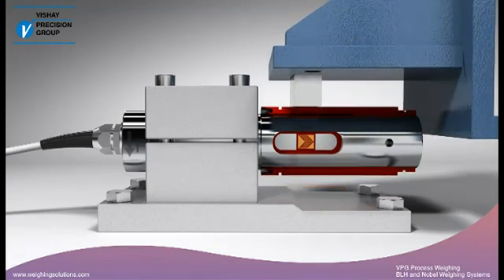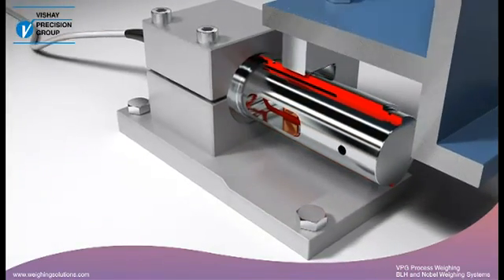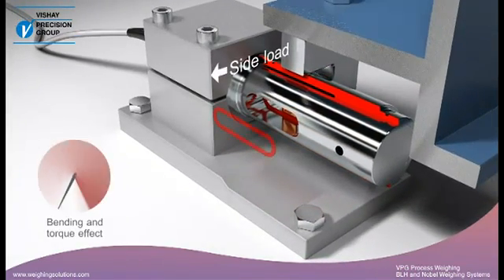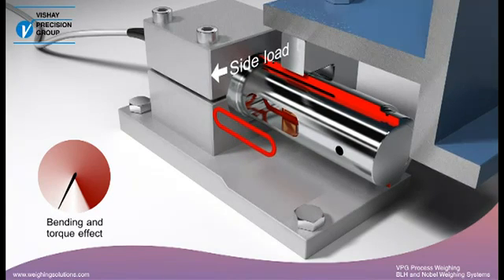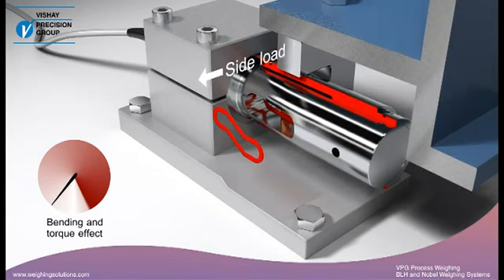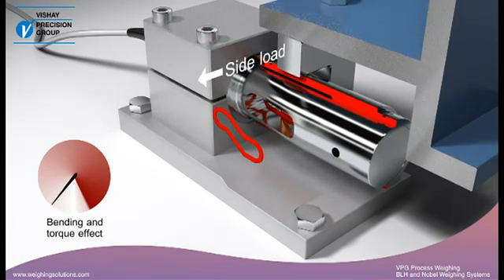The beam behaves in a similar way when subjected to side loads. This enables the transducer to reject errors caused by thermal or structural movement. Side loads that arise in the transverse direction due to agitation, wind, or structural deflections are similarly rejected.